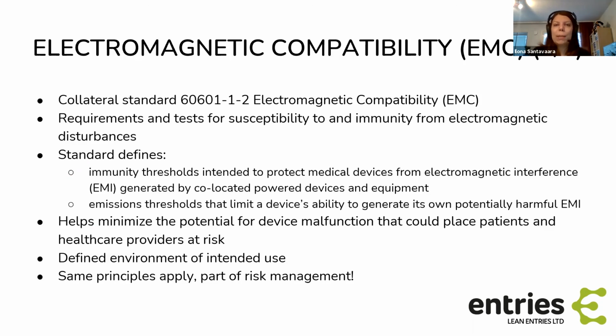And then a couple of slides about electromagnetic compatibility. So as was mentioned, it's its own collateral standard, -2. And it has requirements and tests for susceptibility and immunity from electromagnetic disturbances. So it defines immunity thresholds intended to protect this medical device from electromagnetic interference that is caused by other devices that are used in the same room. And then emissions thresholds that limit a device's ability to generate its own potentially harmful EMI, so it cannot disturb other devices. So it's protection both ways.